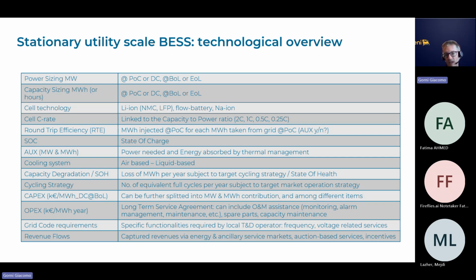One of the most interesting innovations in terms of technology now is liquid-based cooling of the modules - not air cooling anymore, but much more efficient deionized water liquid cooling. Typically it's a fluid-dynamic circuit underneath the module, but in some cases I've seen batteries immersed into a liquid tank to keep them cold.